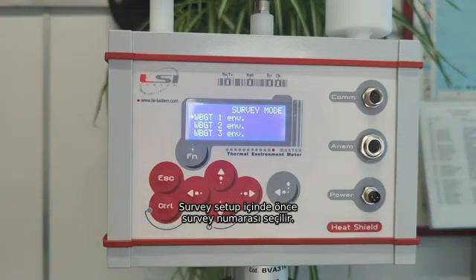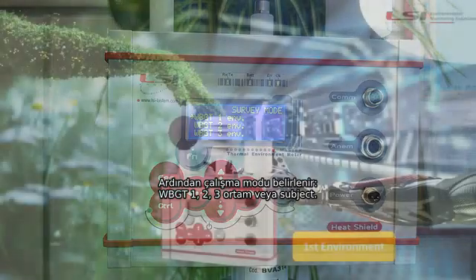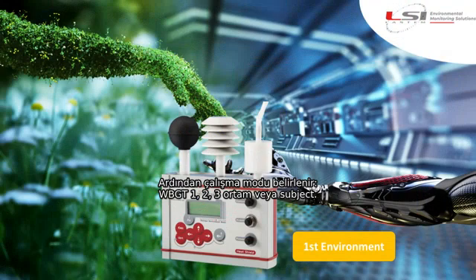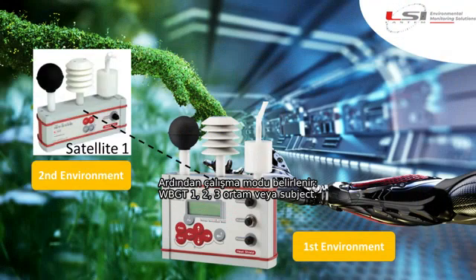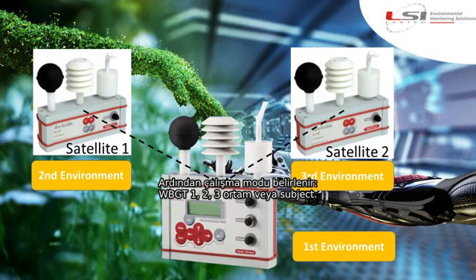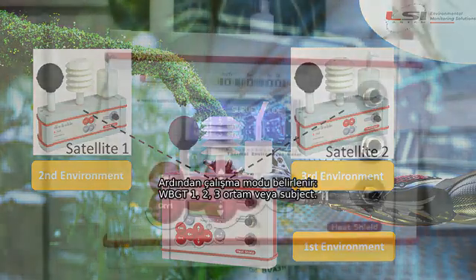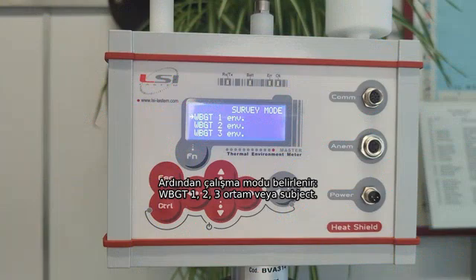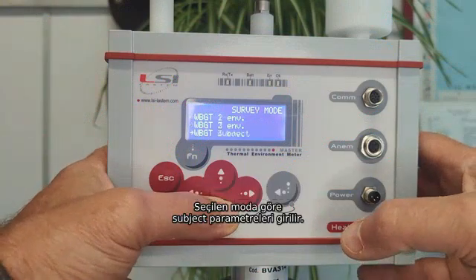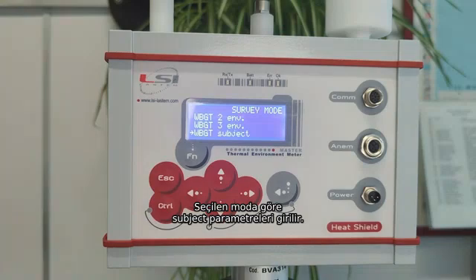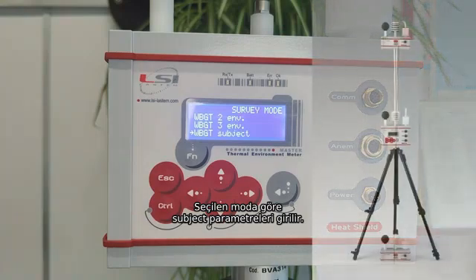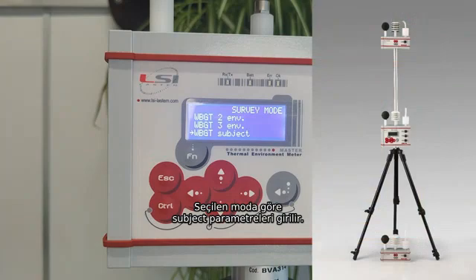WBGT 1, 2, and 3 correspond to the number of environments we wish to analyze. 1 environment if we have only the HeatShield base unit, 2 or 3 environments if we have 1 or 2 additional satellite units. WBGT subject is used if 3 WBGT values on the same vertical are needed: head, torso, and ankle, obtaining one average value of the 3 measurements.